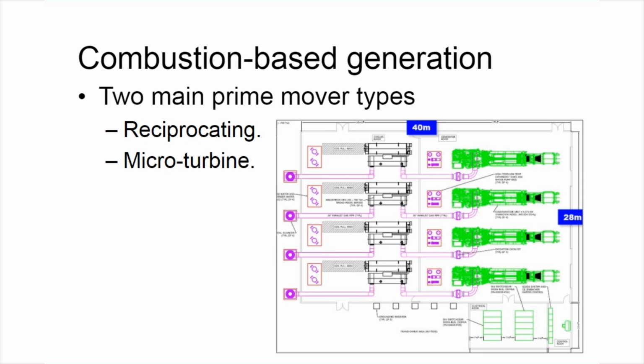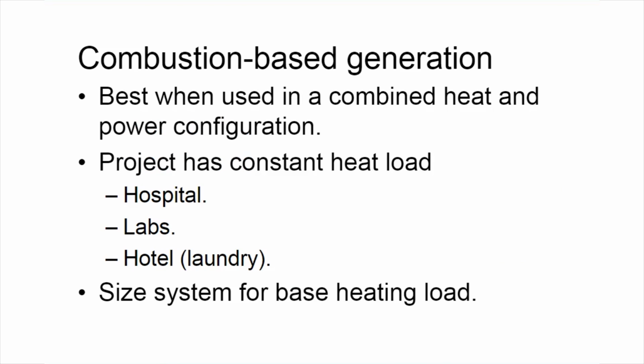As far as the combustion-based generation type systems that you could put with either of those project goals, the two main ones that we look at are reciprocating engines and gas turbines or microturbines. And they both have different reasons that you would want to apply them. These systems are best when used in a combined heat and power configuration, like I mentioned before, but you could potentially use them just as a straight standby generator. But really, the ability to utilize the heat load that's coming off of it matters, and specific building types such as hospitals, labs, and even hotels that have really high laundry loads can utilize that heat year-round. So you want to maximize the hours that you can use both the electricity and the heat that's being generated from the system. So typically we want to size those for the base heating load so that it can run at full load the whole time.